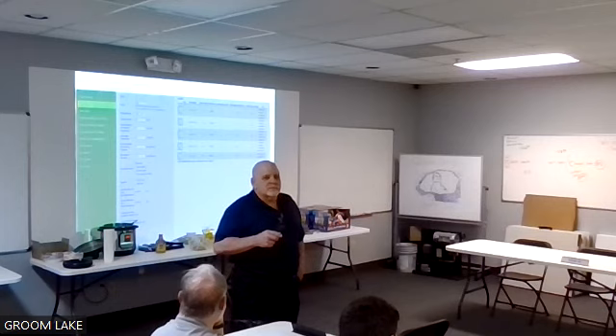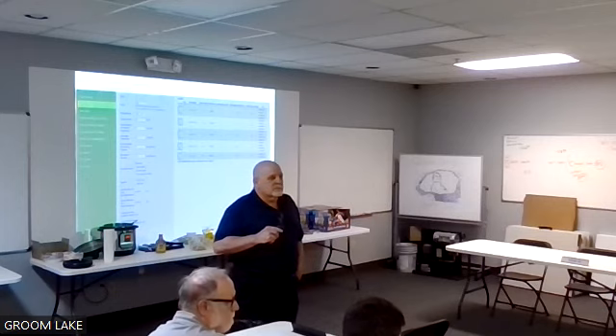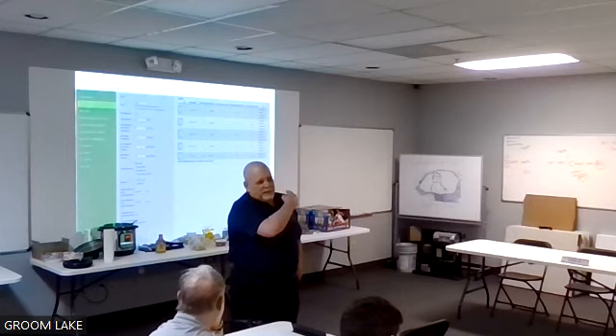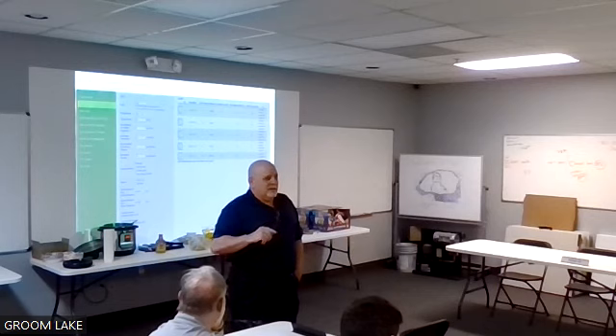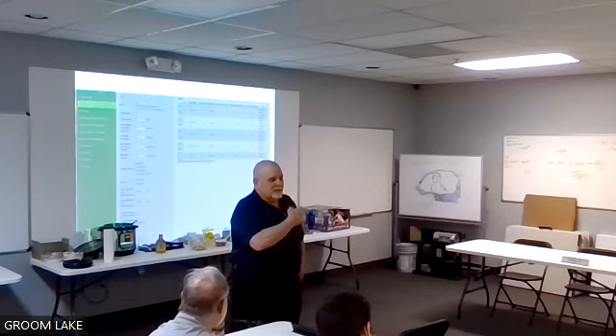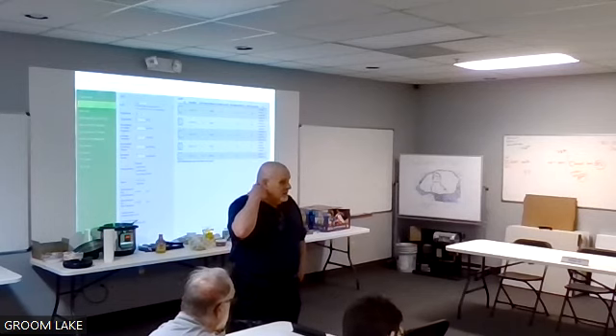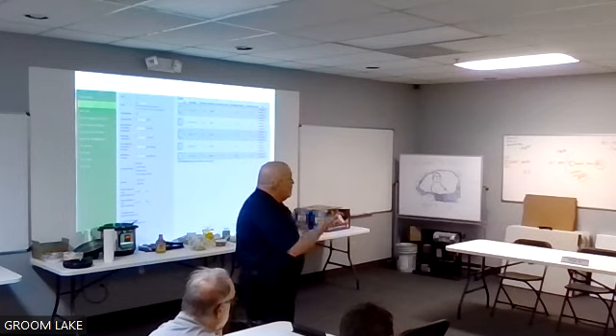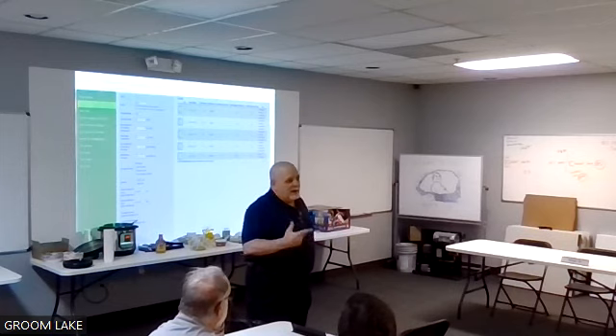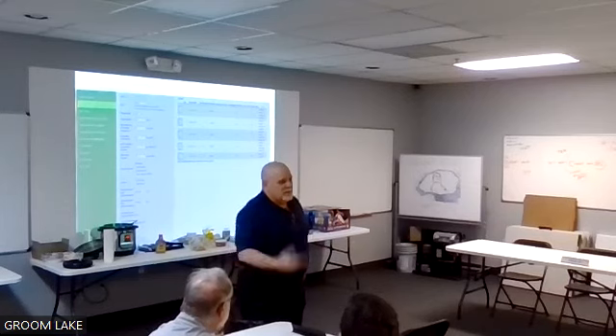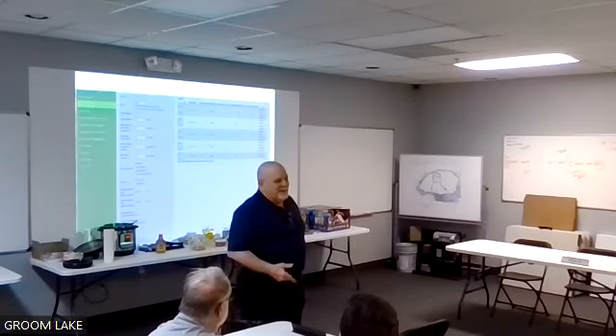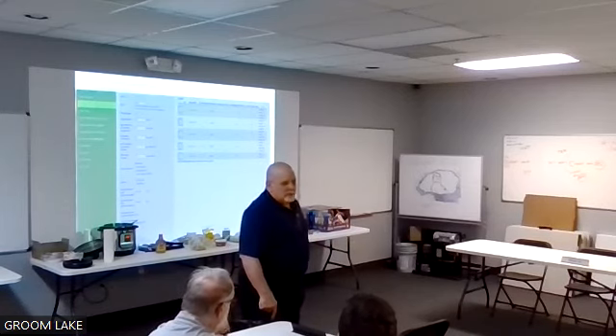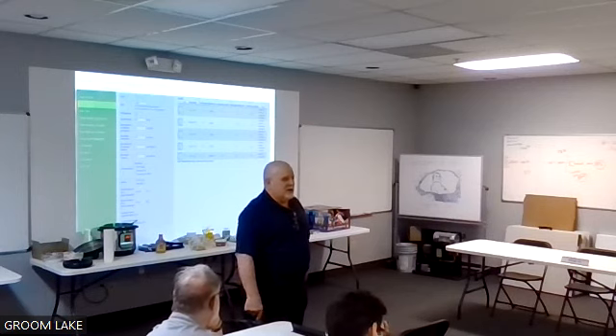There's your tank. And it doesn't matter what the actual total volume of the system is. This is so forgiving. I've used this for 34 years and I've never had it be wrong yet. There's a lot of fudge in here. But if you go above like 20, 25 pounds of fill pressure, call us, because it gets different. But just at your average 2-3 story building, you can use that equation all day long.